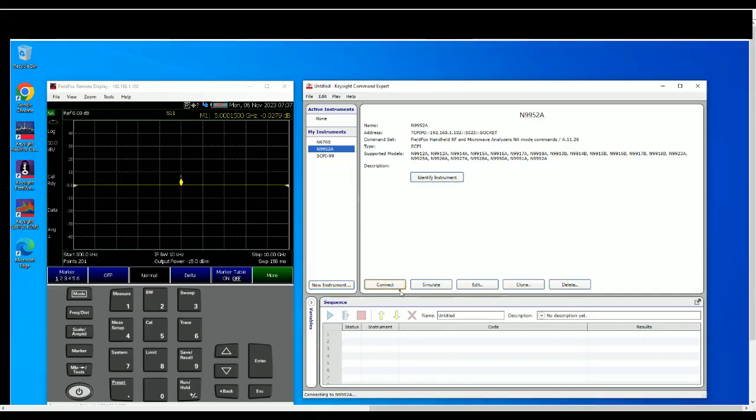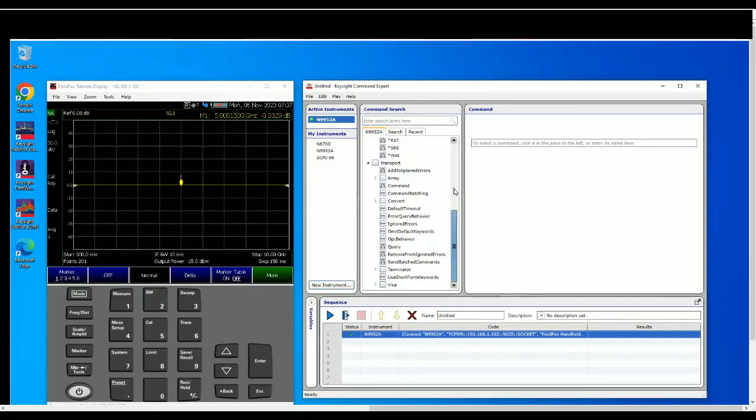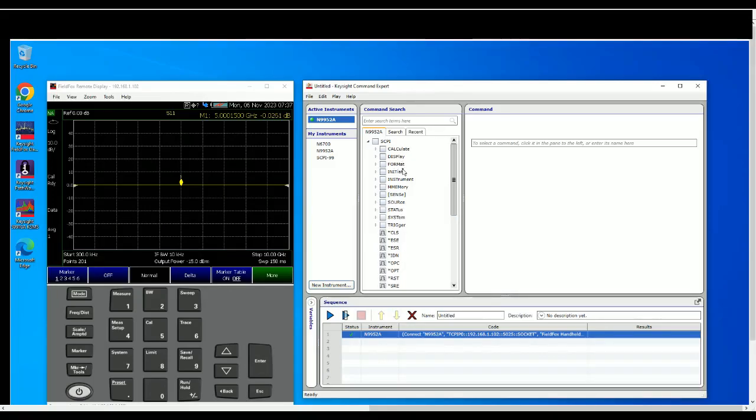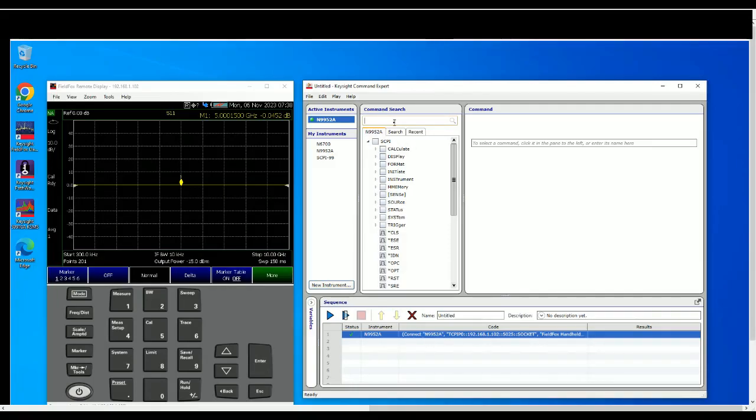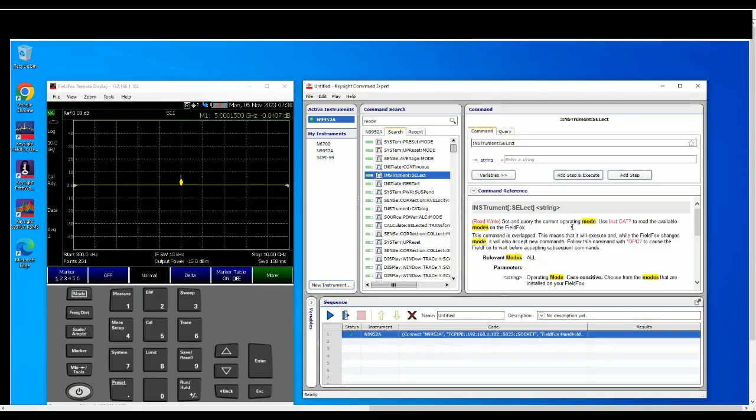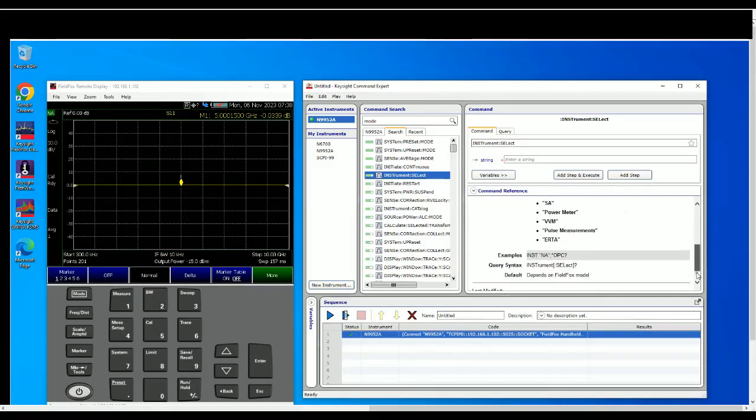So this is all the commands that's available in FieldFox for network analysis mode. So there's a lot of commands here. For now I'll just show you a few SCPI commands that we're going to use commonly to do the setup and also retrieve the data. Let's start with setting up the instruments so we want to make sure that it's in NA mode. So let's type in mode... So this is the one, select mode. As you can see, it does put in some description on what is it all about.